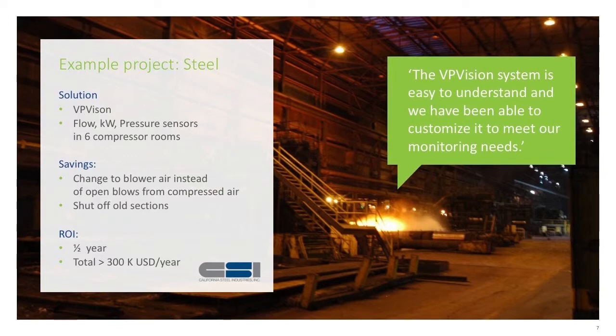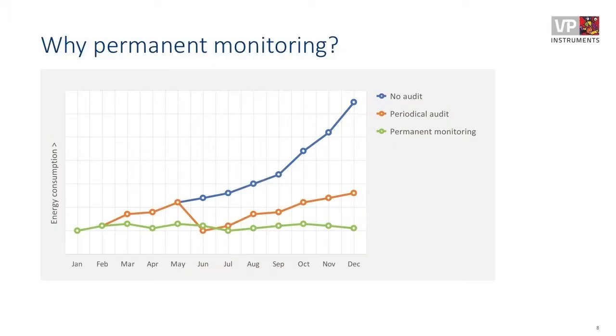So an example, they had a lot of blower air, they had a lot of compressed air basically to use for cooling of ovens, and they made pipes with holes to cool down things, and those were changed into blower air, lower pressure, and with venturi nozzles they were able to reduce the compressed air consumption considerably. They also shut off old sections where the factory was not in use anymore, but there were still pipes running to those sections. So the return on investment in this case was less than half a year. And in terms of money, it was in excess of $300,000 a year savings, which are monitored by the VP Vision monitoring system permanently. And why permanent monitoring?